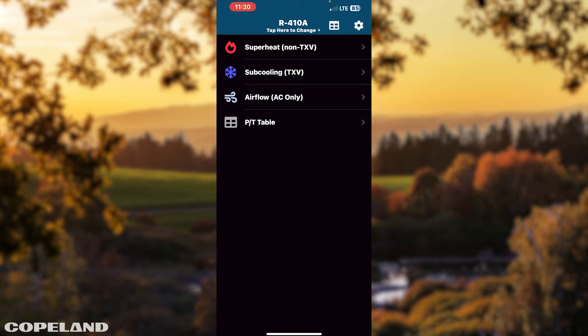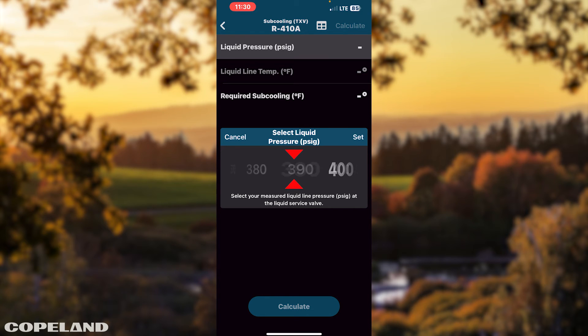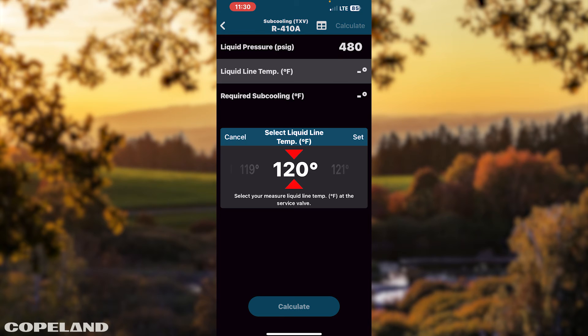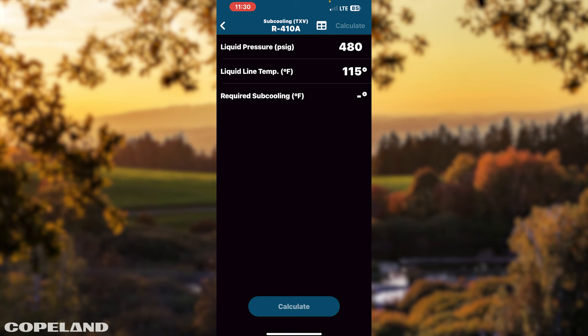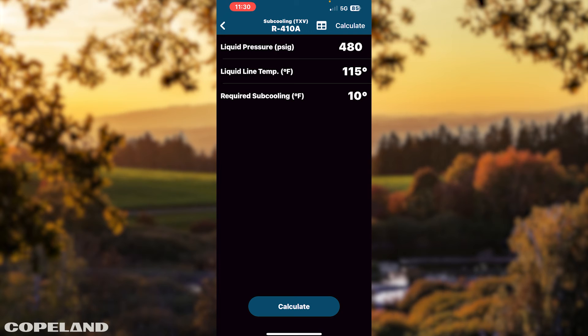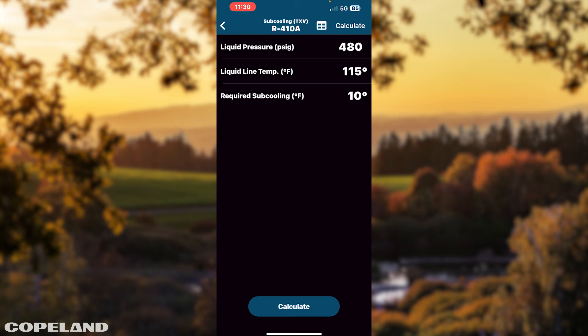To check your subcooling, tap Subcooling. Tap Liquid Pressure. Scroll left or right to your pressure, then tap Set to enter your pressure. Tap Liquid Line Temperature. Scroll left or right to select your temperature, then tap Set. Tap Required Subcooling. Scroll left or right to your temperature. Tap Set to enter your temperature. Tap Calculate at the bottom of your screen. In the system status window, follow the charging instructions. Tap the arrow to return to the subcooling information page.